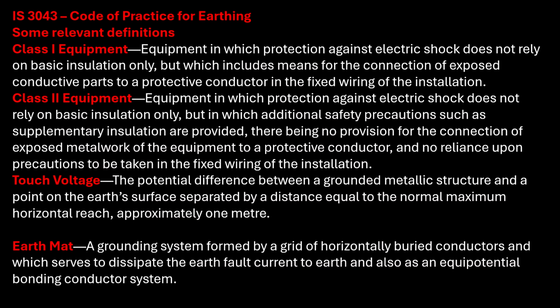Next is touch voltage. The potential difference between a grounded metallic structure and a point on the earth's surface separated by a distance equal to normal maximum horizontal reach, approximately 1 meter. There is something like earthing mat, a grounding system formed by a grid of horizontally buried conductors and which serves to dissipate the earth fault current to earth and also as an equipotential bonding conductor system. The earthing mats have been provided in most of the underground metro stations.